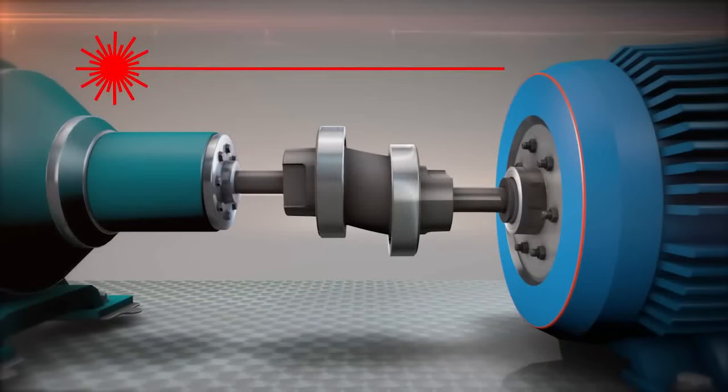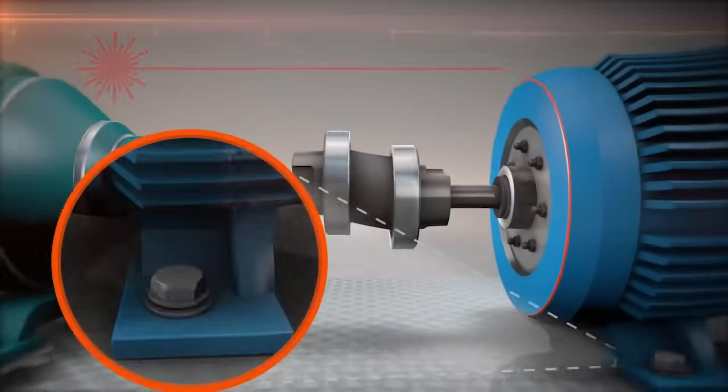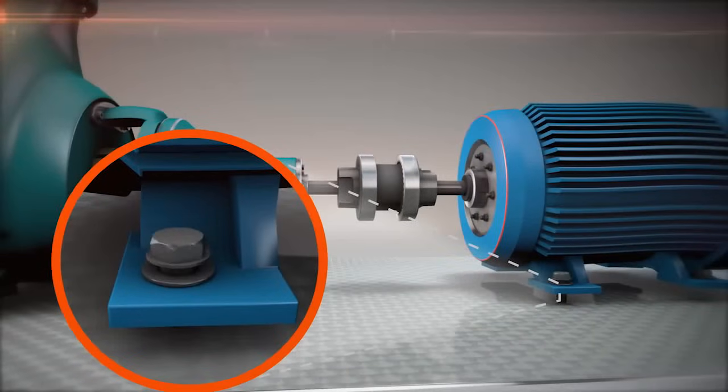To determine which type of soft foot a machine has, we can use laser alignment systems to measure the amount of movement a soft foot produces at the shaft center line when loosening or tightening a foot.